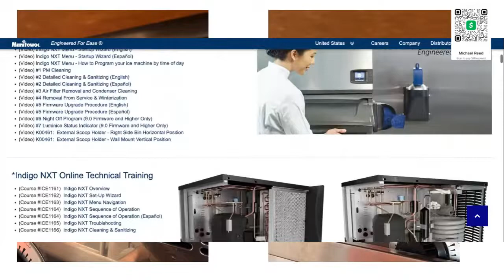These are free. In this online training module, you will learn the Indigo Next ice machine cleaning and sanitation, including removal of parts, cleaning and sanitizing the parts, interactive cleaning sanitizing sequence of operation, and winterization. We'll go through each topic starting with removal of parts. It's recommended that the cleaning sanitizing procedure be performed a minimum of once every 6 months. The end user is responsible for maintaining the ice machine in accordance with the instructions listed in the Installation Use and Care Manual. Indigo Next, removal of parts.